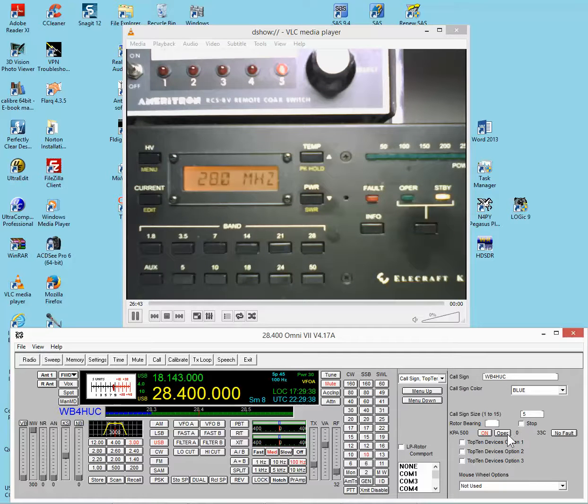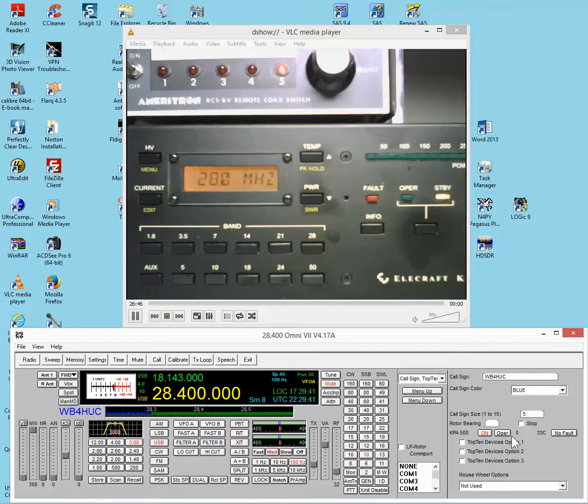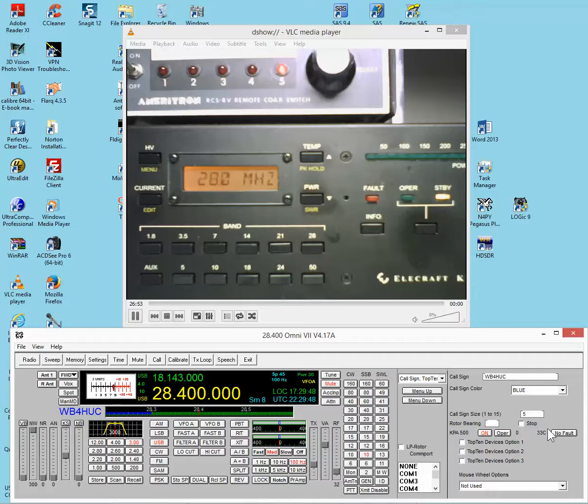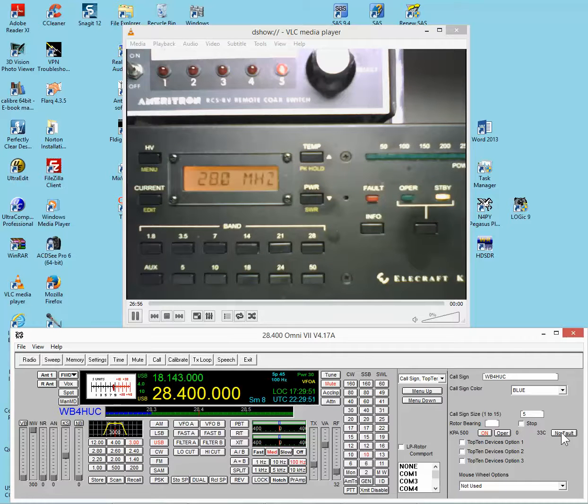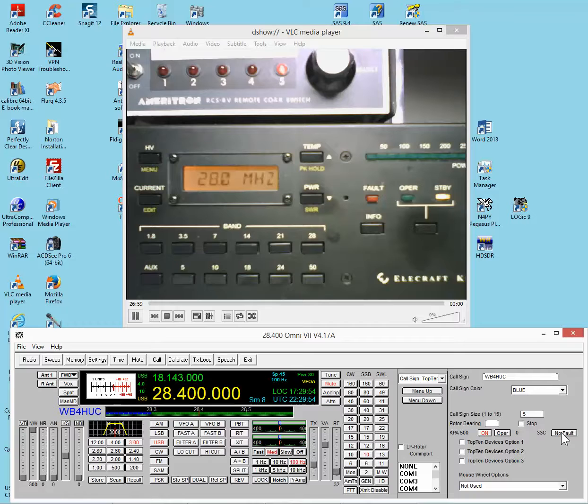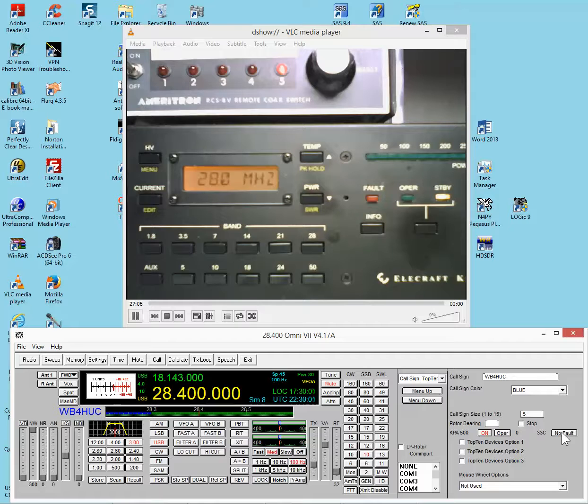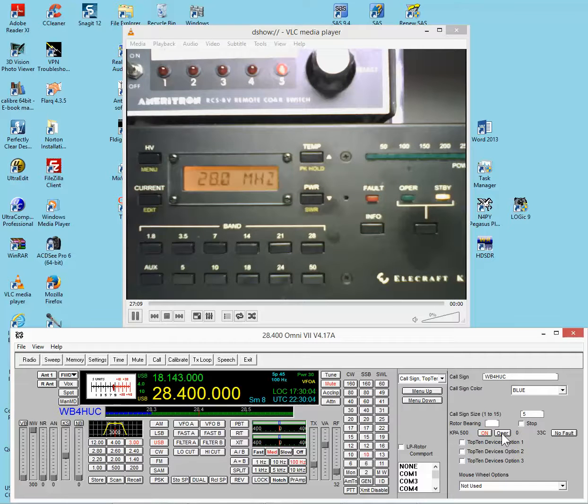Next to the operate button is a number that will display the power output of the amplifier. The next number will display the operating temperature of the amplifier in Celsius. And then this button will display any fault codes that the amplifier generates. And you can click the button to clear those faults. It'll put the amplifier back in standby mode. And then you can click the button to put it back into operate mode.